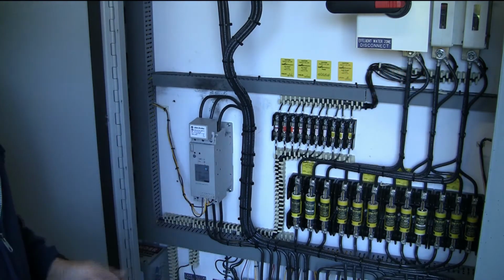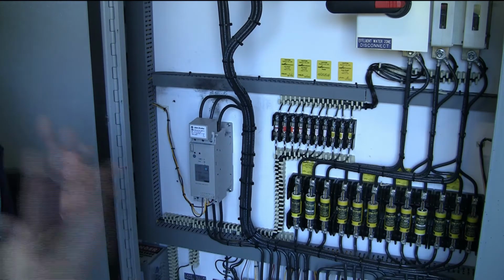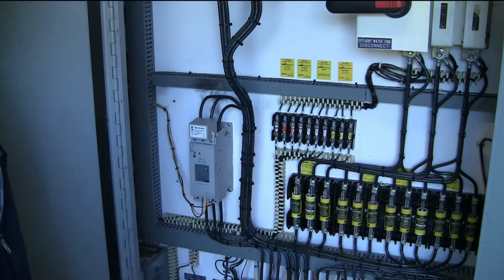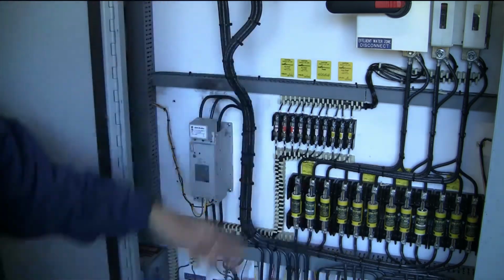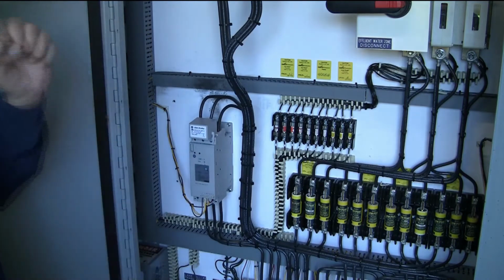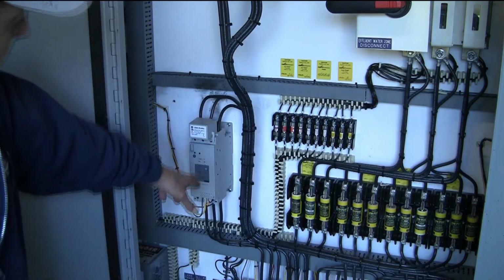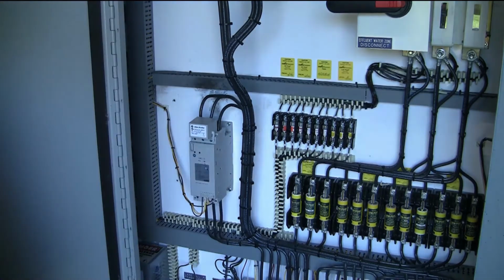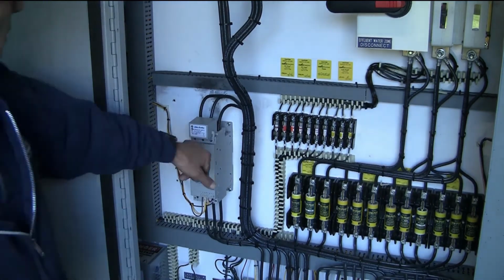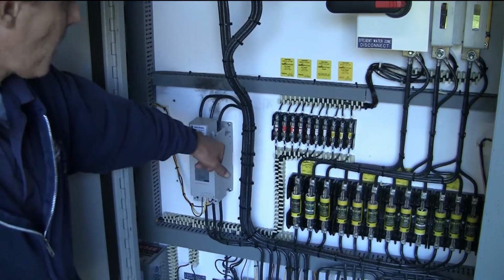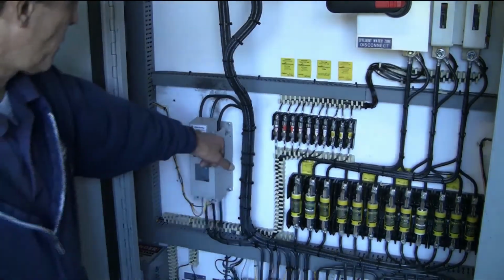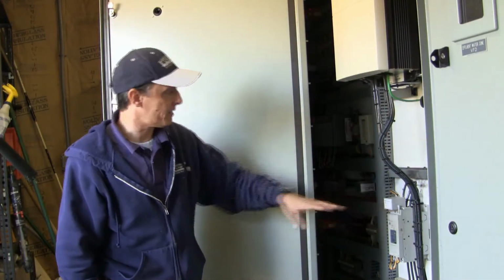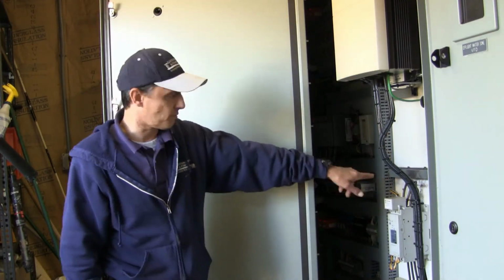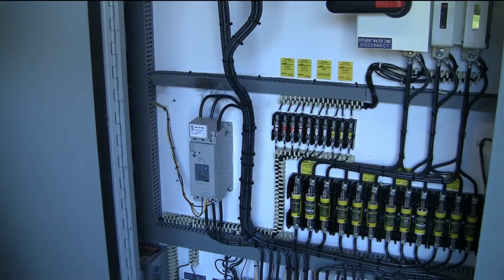One of the things that happens, especially if you have a voltage problem in the area, lightning, transformer, sometimes there's an accident, somebody hits a pole and a transformer blows up, sends a surge through. You can see where it's black behind this, what's called a soft starter. Now, they took a surge, there's a surge protective module on top, and that's kind of what it's made for. This one's good, but the previous one took a hit and blew up, and you can see the remnants of the black stain on the wall behind it.